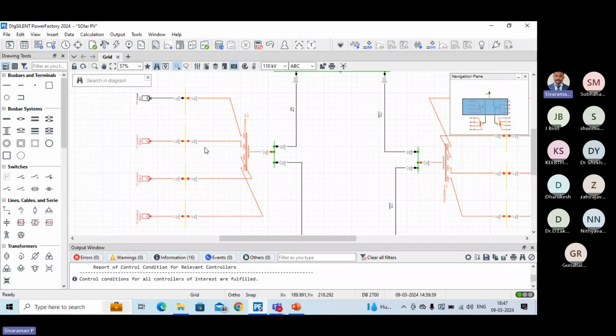The next step is how we are going to get the 12.5 megawatt inverter block capacity. I explained two options. One option is 4 numbers of 3.125 MVA inverters connected to one five-winding transformer, which has one HV winding and 4 LV windings. The second option is two numbers of 6.25 MVA transformers with 2 LV windings each, so by combining two of them we can get 12.5 megawatt. For doing that, we have to do some techno-commercial analysis, and based on that we arrive at the value.